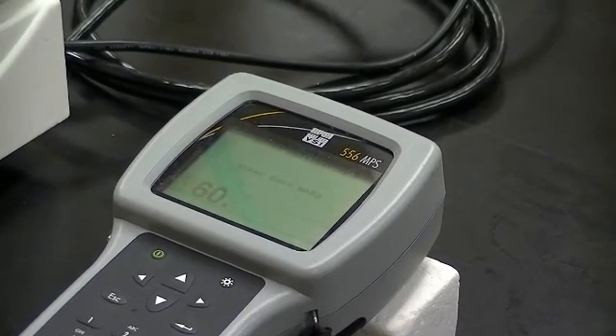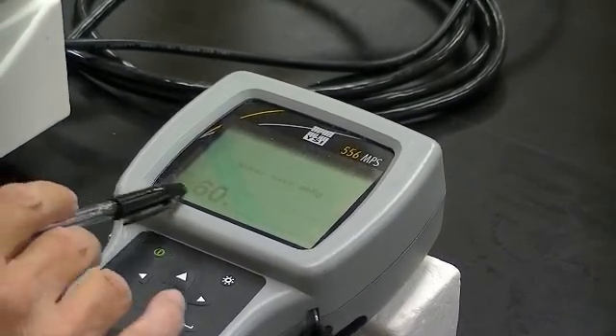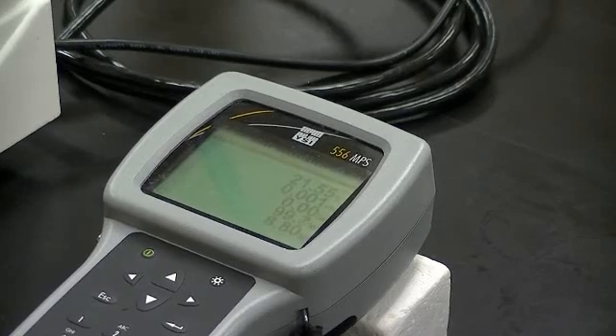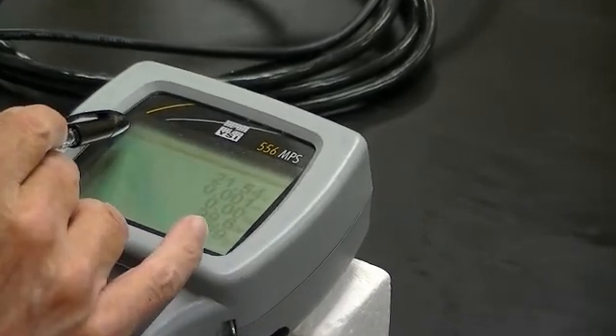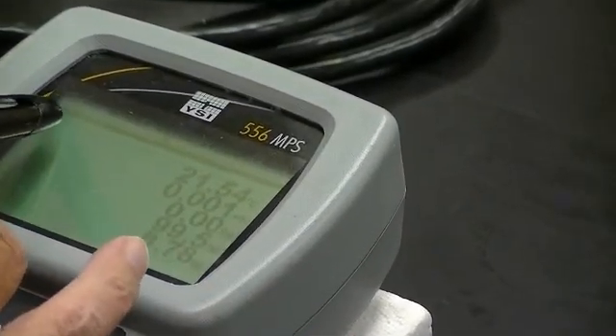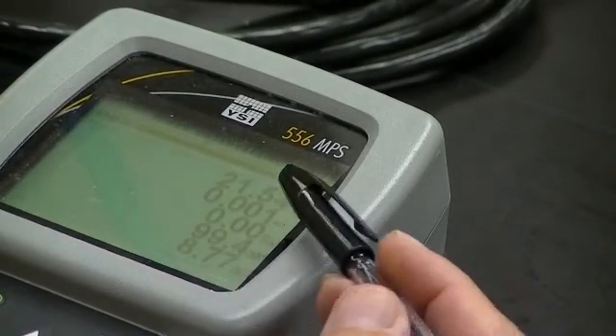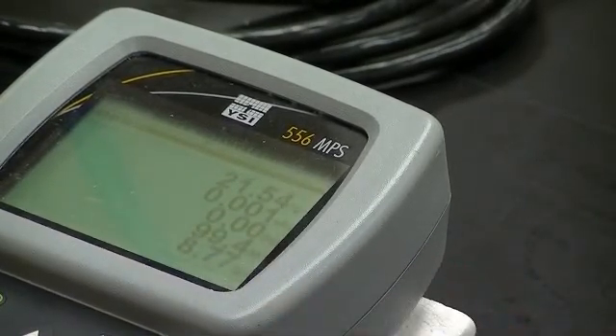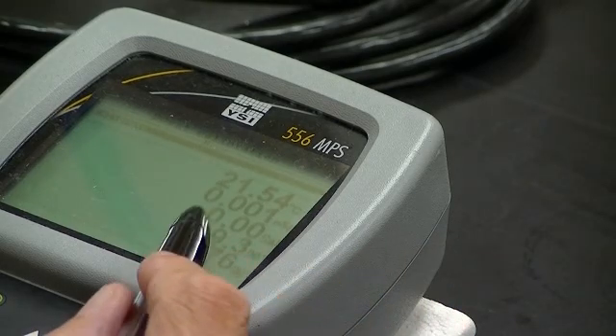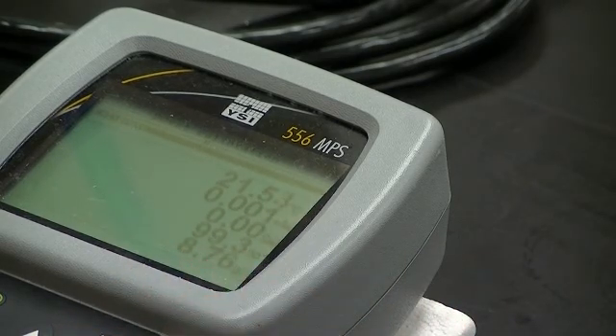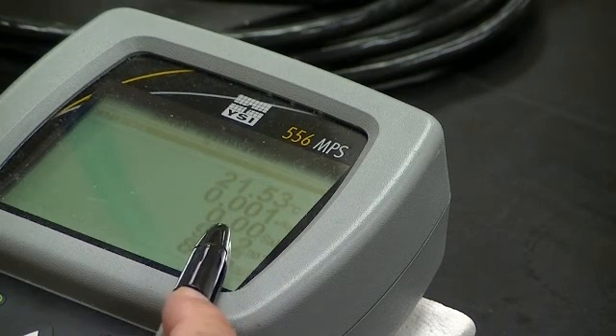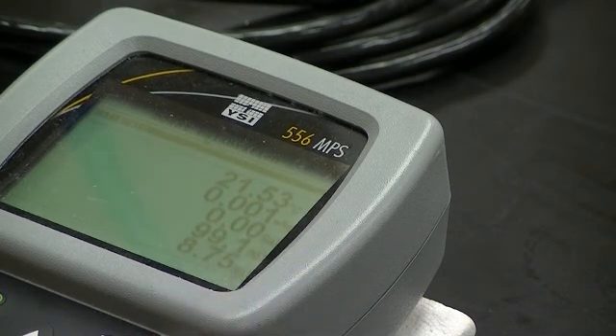Now at this point you could enter an atmospheric pressure if you had a barometer. We don't, so we'll leave it at 760 torr, which is close. All right, now you have the calibrate screen. Now you probably can't see it in the video, but the black darkened line right across the top says calibrate. And here you have your same display as you did with the run screen. And now this is saying 99.3% DO. And of course that's close. We want it to be 100. So we wait for a few seconds to see that stabilize.